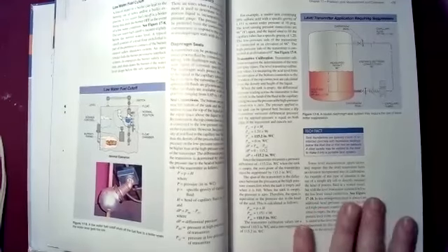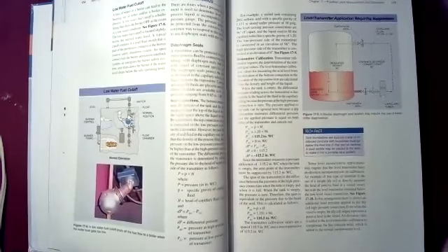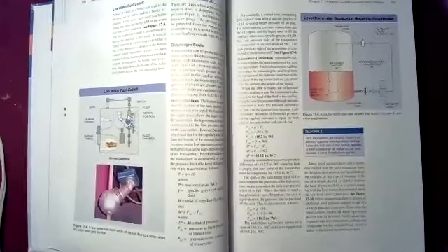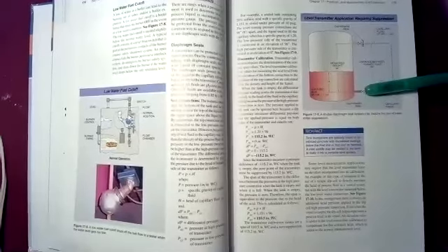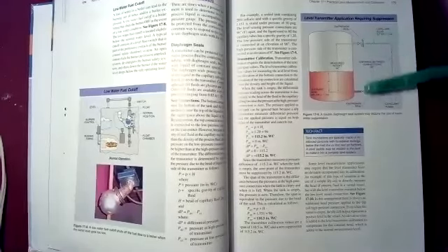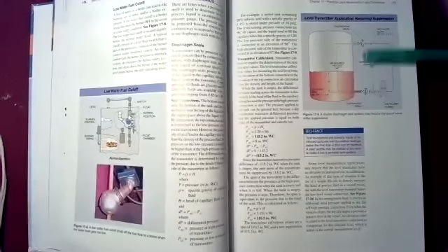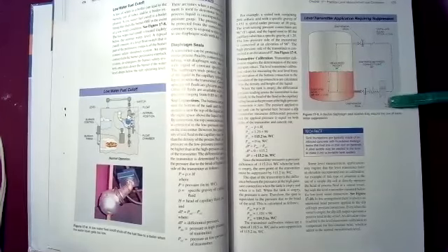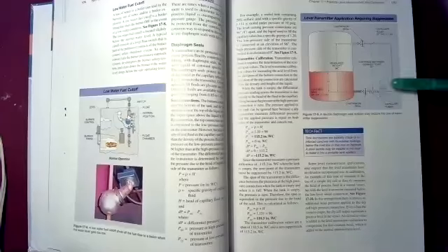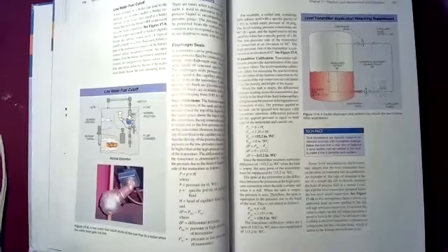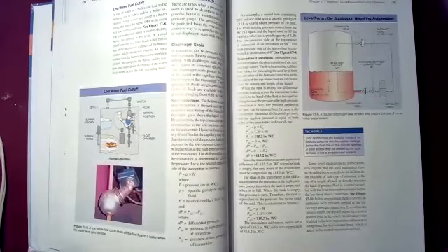And one way to deal with a corrosive liquid is you use something like a very high-tech corrosive resistant diaphragm seal. And they give you a couple possible applications for a diaphragm seal application where you've got a point at the bottom of the tank where you would be measuring the pressure, and you compare that to a point at the top of the tank where you're measuring the differential pressure. That column difference is measured up, and you're protecting your measurement system. Your capillary and your high and low pressure measurement device is completely isolated from that dangerous sulfuric acid that they mention on page 175.